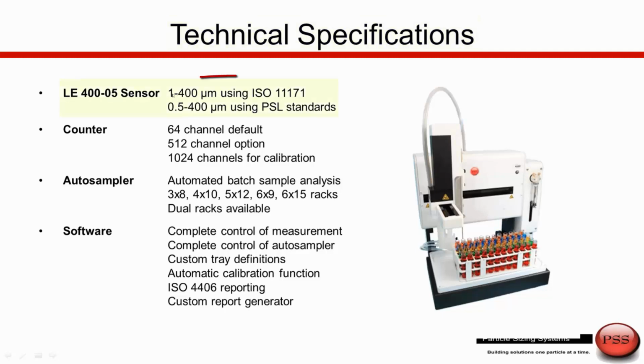If we use the extinction only calibration, the dynamic range is 1 to 400 microns. We can measure down to smaller size ranges for other applications, down to 0.5 microns if we use the summation calibration. There are many more channels of size information than required for the applications we're discussing today, but we can choose, do we want to look at the data in anything from 1024 down to 64 or fewer size channels. When we talk about the auto sampler, we also talk about the trays, and we can have 1 or 2 trays, and we have different racks available depending on the throughput, and also just what size tubes perhaps are already used in a laboratory, or what size tubes are appropriate for a given kind of application.